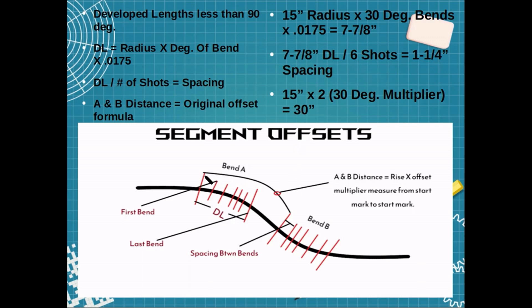For the second bend, measure 30 inches from the first mark of Bend A — that's your start mark for Bend B. Do the same: seven and seven-eighths for developed length, then go back to the first mark and lay out an inch and a quarter apart. Reminder: your first mark is not a bend mark — you start bending from the second mark. I mark my conduit all the way around from the second mark so I don't get confused.